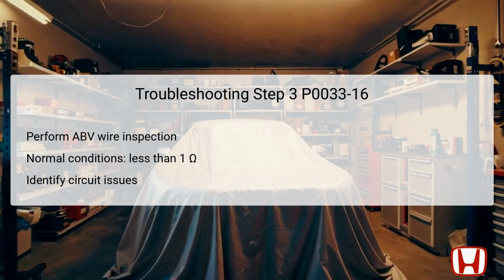Once the connections are properly disconnected, the technician should perform an ABV, air bypass valve open wire inspection. This step involves measuring the resistance across the isolated terminals of the turbocharger bypass control solenoid valve and the PCM connector. Normal conditions dictate that the resistance should be less than 1 ohm. A resistance reading above this threshold could indicate an open circuit or continuity issues within the wiring. If the measurements reveal abnormal circuitry, the technician should investigate further into the harness and connection points for signs of wear, fraying, or disconnections that could be contributing to the malfunction. If the circuit appears intact, then attention should shift to the PCM for possible internal faults.